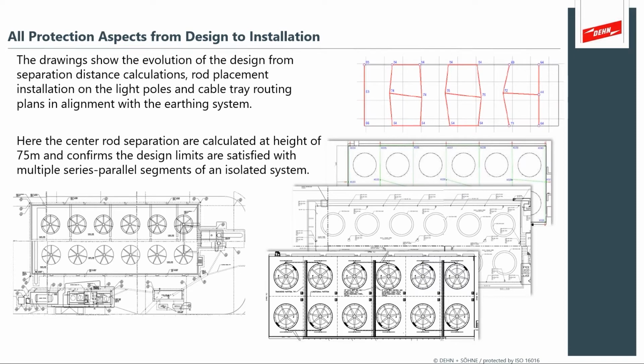And then we overlay that with the grounding pigtails so that we know that the routing of the cables will be acceptable for the customer. The customer doesn't want to have exposed cables for trip hazards across the deck of these cooling towers. And so we'll target to use an isolated conductor in the suitable cable trays that are on these systems. And so this is an illustration showing where the customer's cable trays will run the motors and the earthing system and the control systems for all these turbofans as part of the cooling.